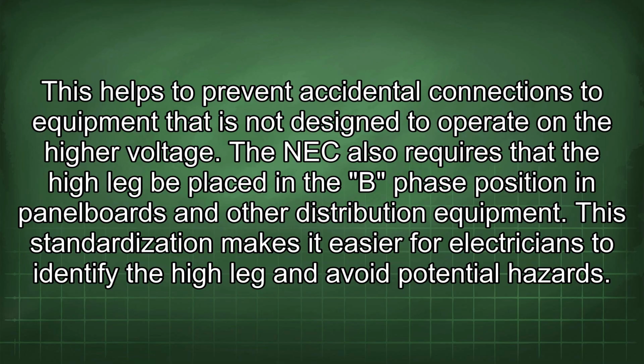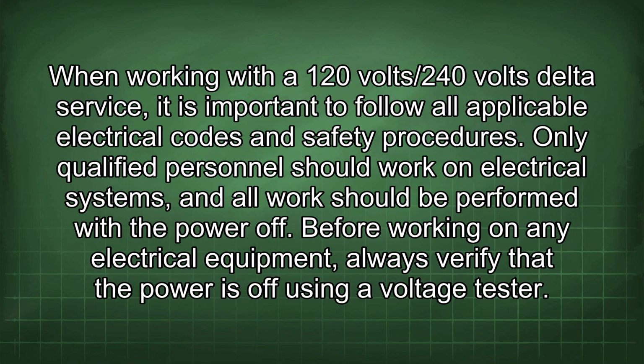The NEC also requires that the high leg be placed in the B phase position in panel boards and other distribution equipment. This standardization makes it easier for electricians to identify the high leg and avoid potential hazards. When working with a 120-volt/240-volt delta service, it is important to follow all applicable electrical codes and safety procedures. Only qualified personnel should work on electrical systems, and all work should be performed with the power off. Before working on any electrical equipment, always verify that the power is off using a voltage tester.